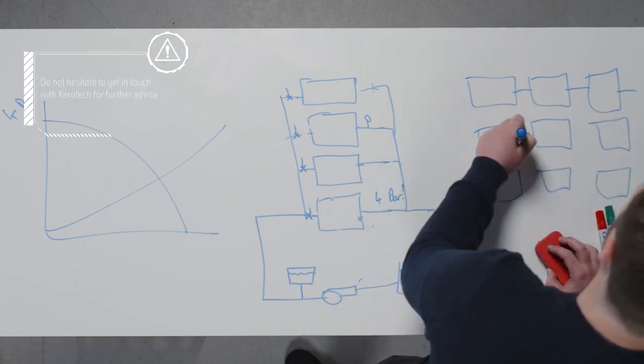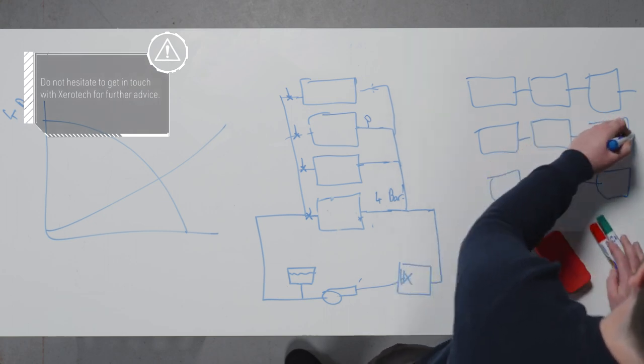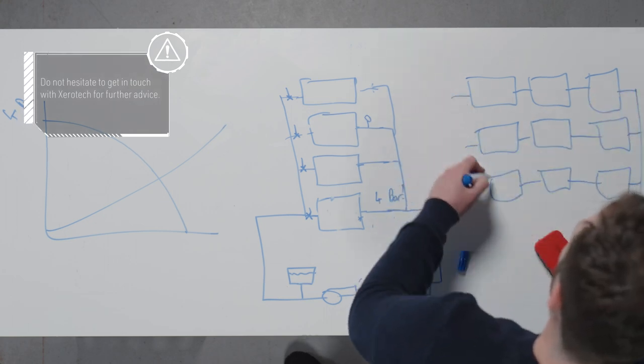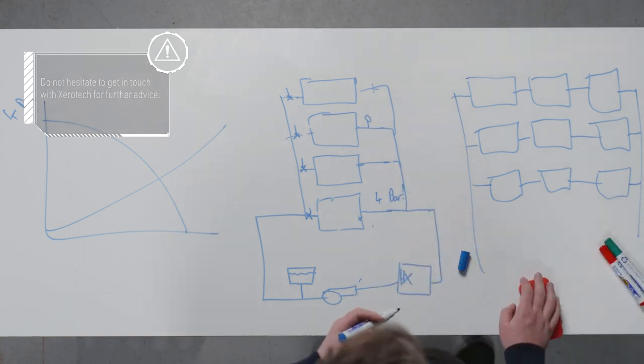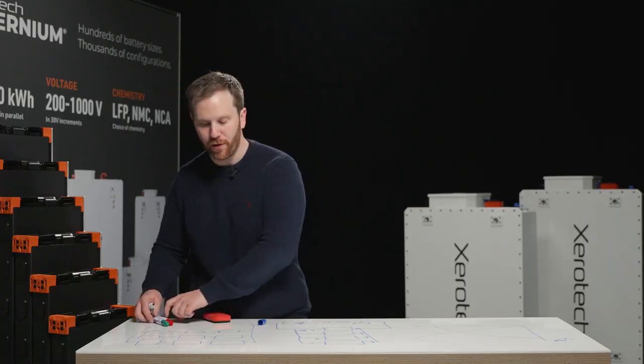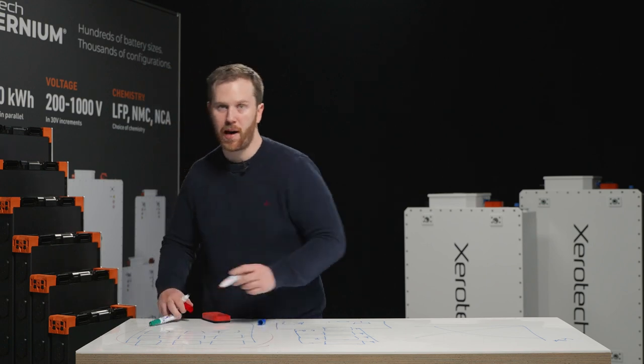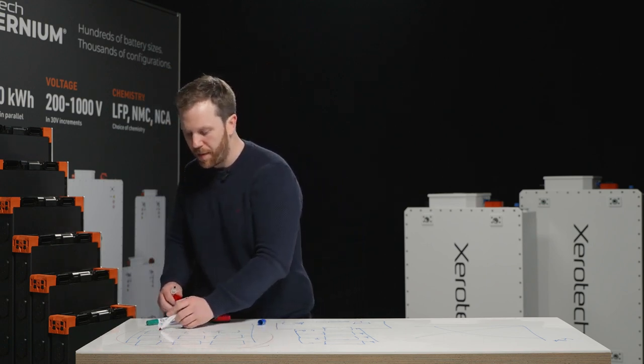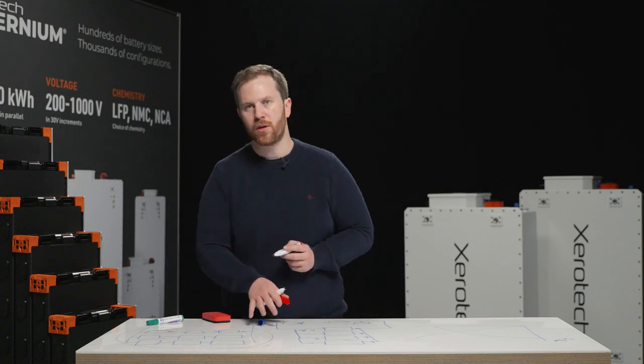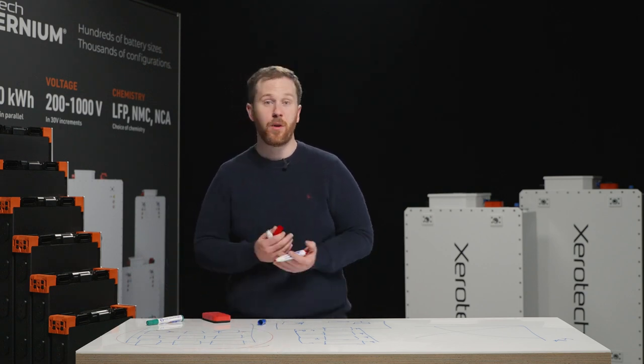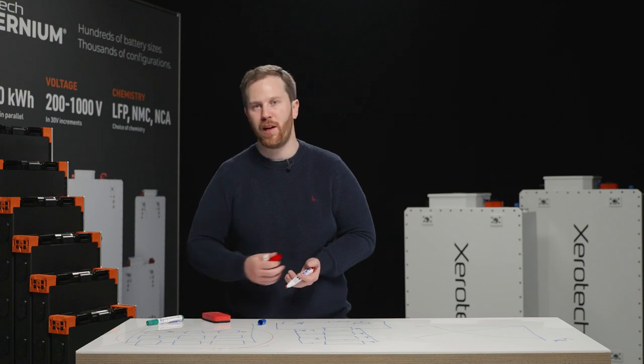There's a lot of considerations for large-scale multi-pack plumbing applications, and we'd strongly encourage you to contact Xerotech for advice and guidance on this. There are certain considerations you want to take into account during failure modes and many other factors. If you've got one single system, all in hydraulic parallel, if you have a failure of a battery pack or a thermal event in one battery pack, it could contaminate the cooling system of the entire pack architecture. Or if you have a leak in a pack, a pipe, a valve, you could lose coolant from the entire system.